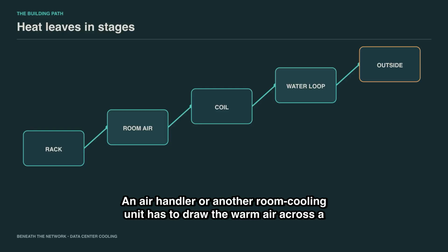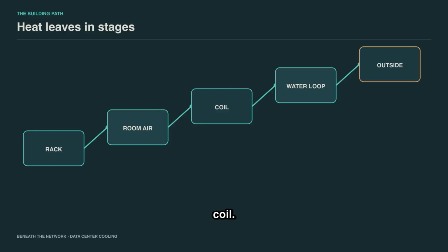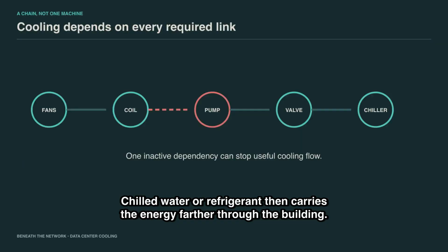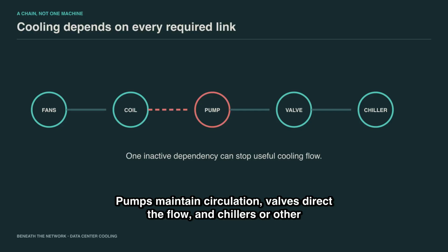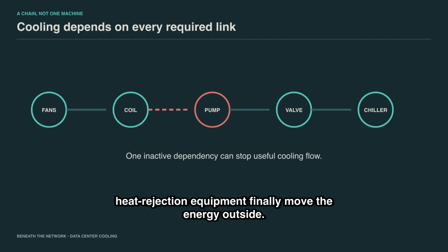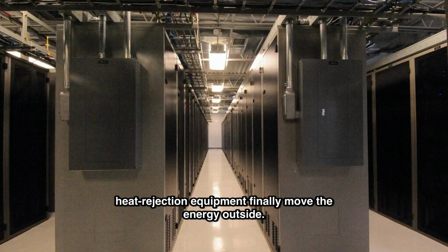An air handler, or another room cooling unit, has to draw the warm air across a coil. Chilled water, or refrigerant, then carries the energy farther through the building. Pumps maintain circulation, valves direct the flow, and chillers or other heat rejection equipment finally move the energy outside. The result is a chain rather than a single air conditioner.